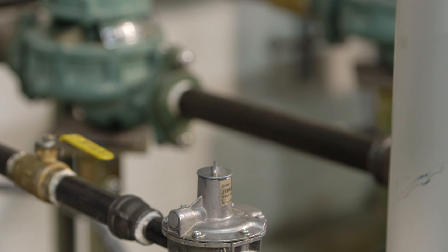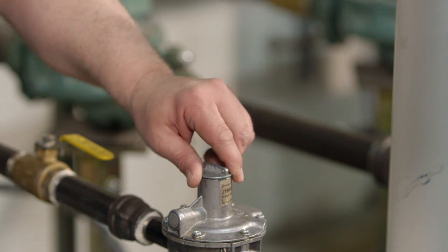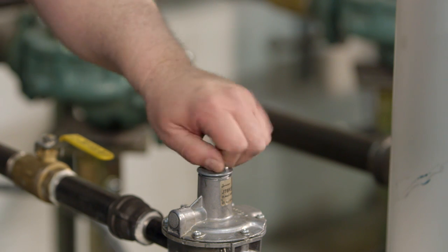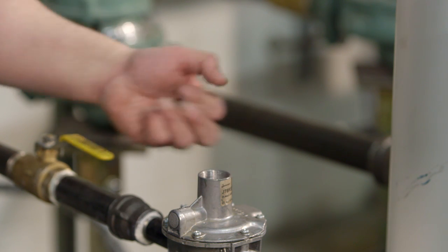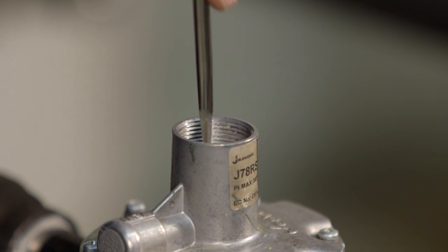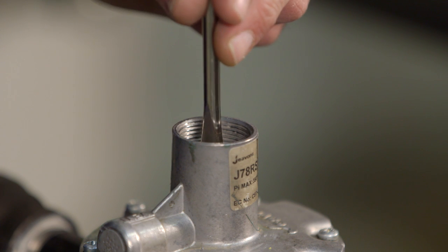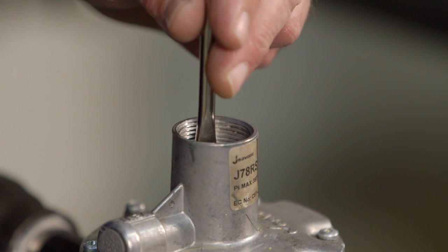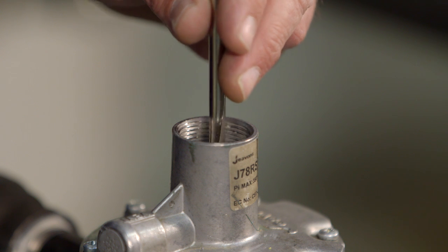If the incoming pressure is too high or too low, adjust it through the gas regulator that leads to the unit. You can do this by unscrewing the cap on your gas regulator and using a screwdriver to turn the adjustment screw clockwise. This will increase gas pressure. Turning counterclockwise will decrease gas pressure.